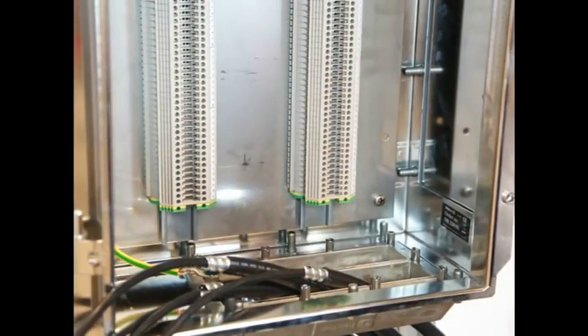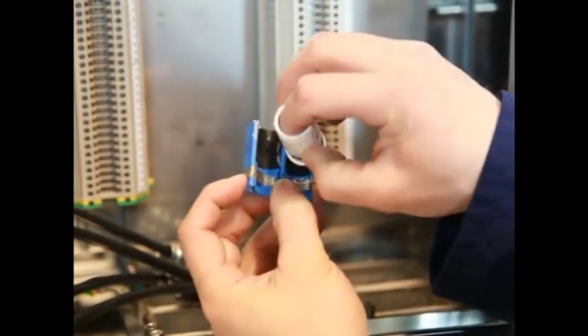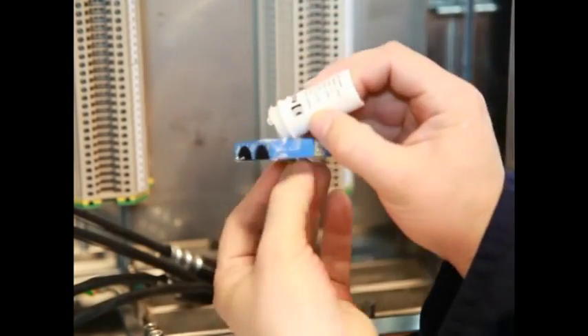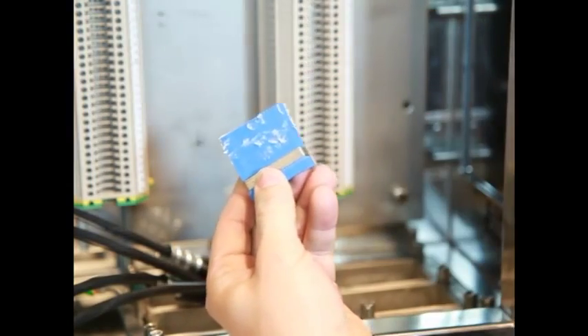Feed the cables through the opening. Even pre-terminated cables can easily be inserted. Lubricate all modules thoroughly on the inside and outside. Avoid excess lubricant on the braid.